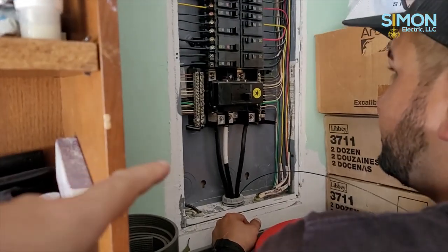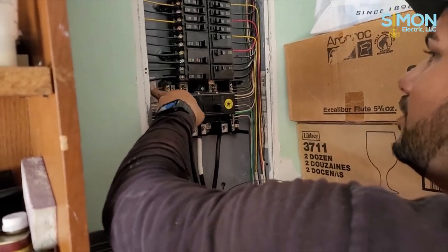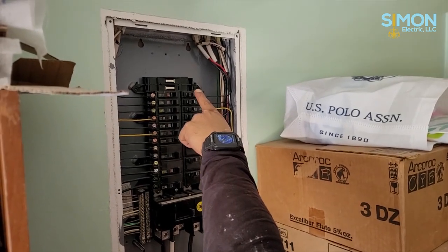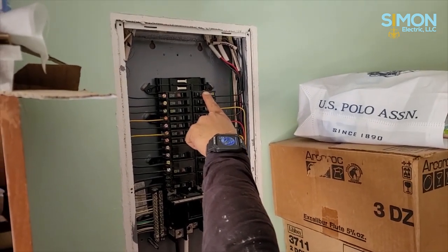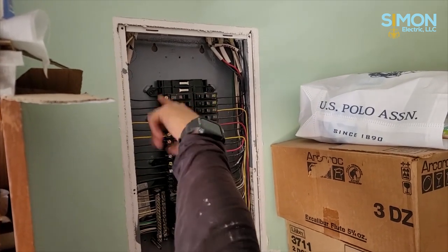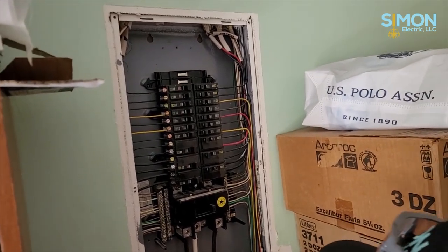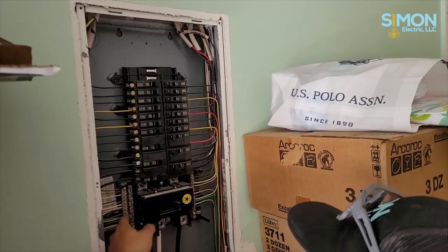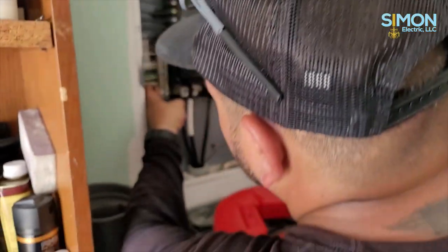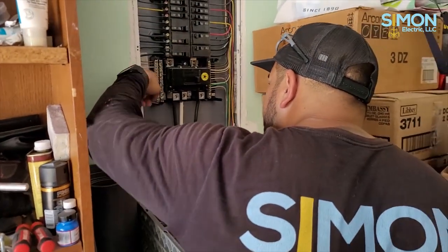So we're going to have to put a new ground bar somewhere in there and take all the grounds off. All right, so they got room. I mean, that's a ground point up there. So if we bring it over up there, we can put a ground bar up there. But you need a Square D ground bar. Well, you could steal one of these ones. Just unscrew it and move it up there. That one doesn't really have much in it, right? No, this one is some 1, 2, 3 grounds. Perfect. And it'll bolt right up there.